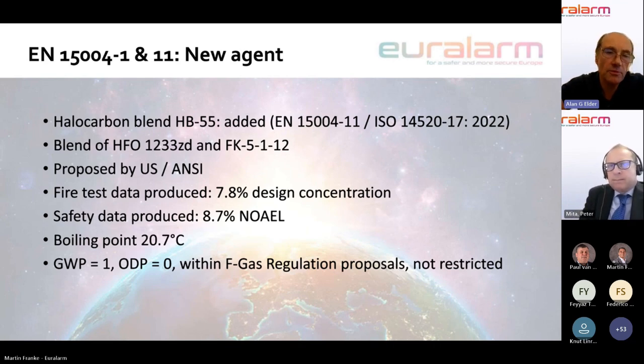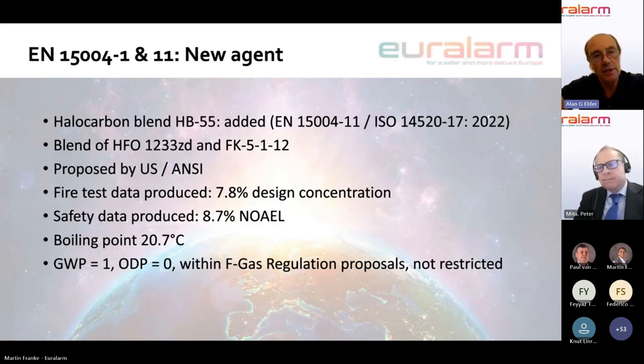Now, just as an update, and I won't spend more time than necessary on this particular agent, the manufacturer of this agent has, at this moment in time, decided not to further commercialise the agent. But I didn't want to omit a change to the EN 15004 Part 1 if you suddenly see EN 15004 Part 11 referenced. You know, that is published. It is mentioned within Part 1, but the manufacturer at this time is not proceeding with commercialisation or full commercialisation. They have actually obviously gone to the stage where they've got all of this important data, but in terms of promoting and further commercialisation, they've put that on hold at this stage. Okay, Martin.